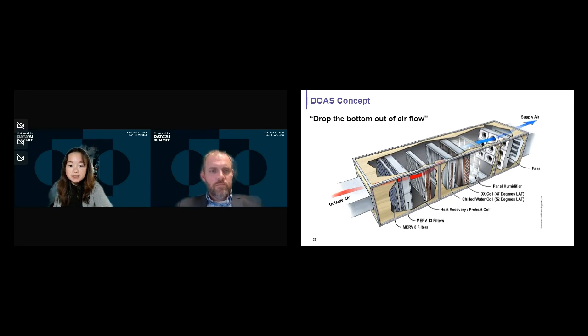The concept of this is to have a chill water coil and DX coil in series, where we have the leaving air temperature at 47 degree dew point, which means when you take in the humid outside Florida air, it really get cooled down and dehumidified to a point that you have dry air. And then we also have the wraparound heat pipe in series with those cooling coils so that we can utilize some free reheat and free preconditioning with our system.